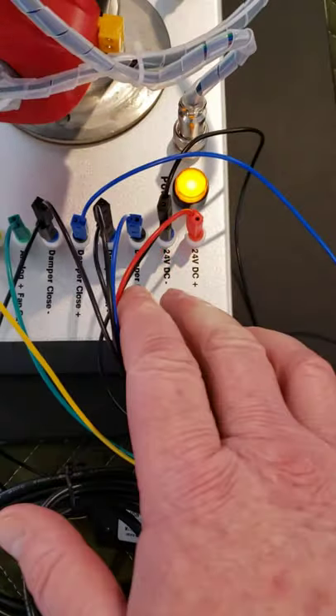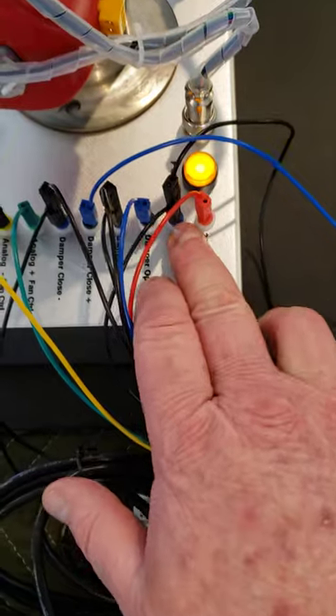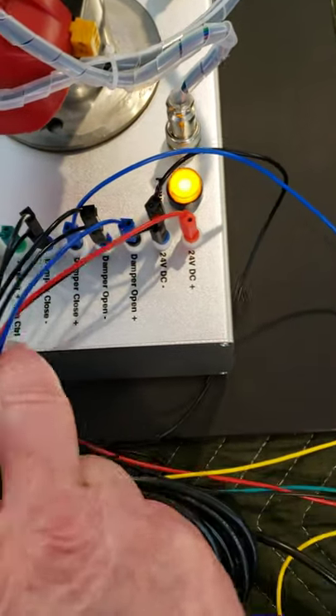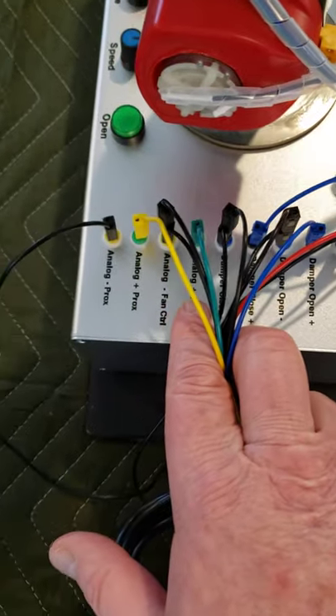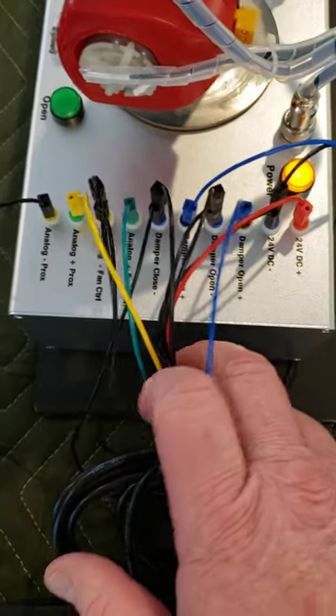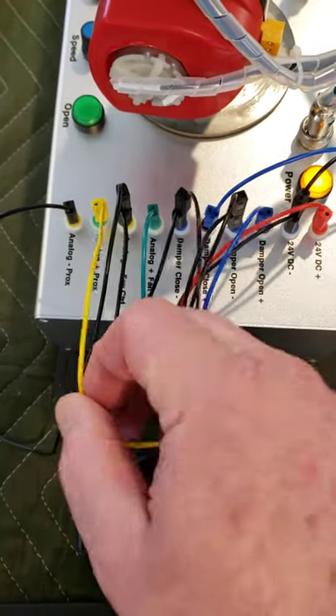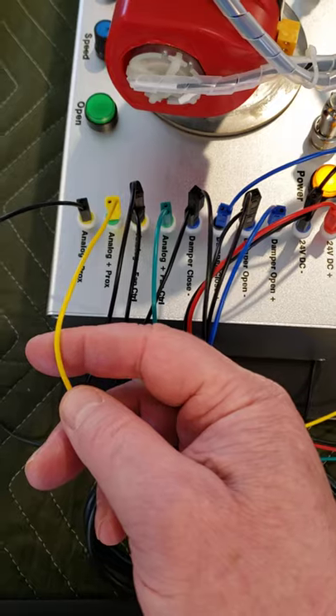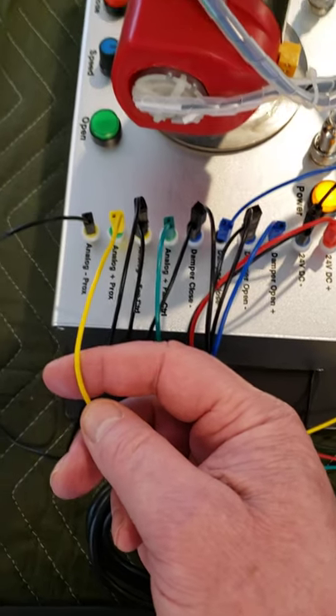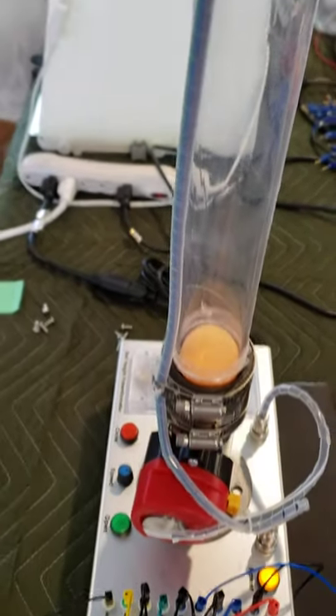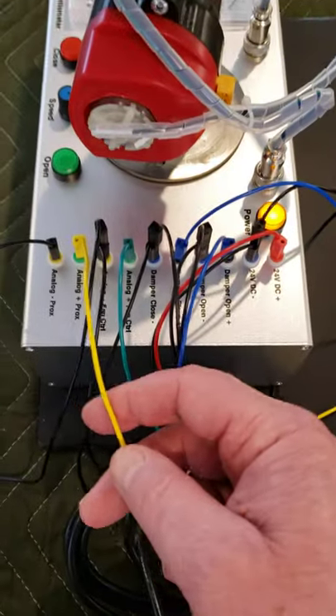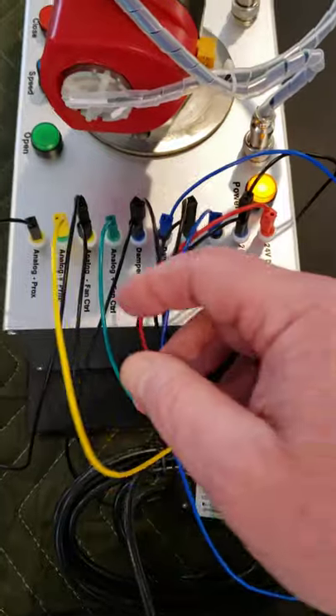So all the negatives, starting from here and every other one, are going to be jumpered together. And that's your common, your 24 volt DC common. This is going to the PLC as an input, saying where the ball height is actually located, or where the ball is being located. The higher it goes, the higher the input goes.